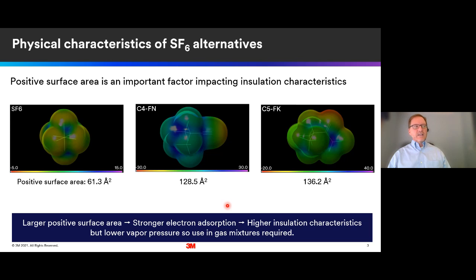But one thing to recognize is that there is a bit of a trade-off here because we've made larger molecules in order to get that electrical performance. These materials have a lower vapor pressure. They're not as volatile as SF6. So as Renee mentioned, these materials are often best used in dilute gas mixtures in order to be able to function over the typical ambient temperature range that would be required in most electric power applications.